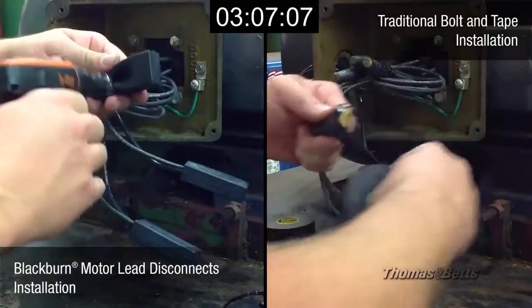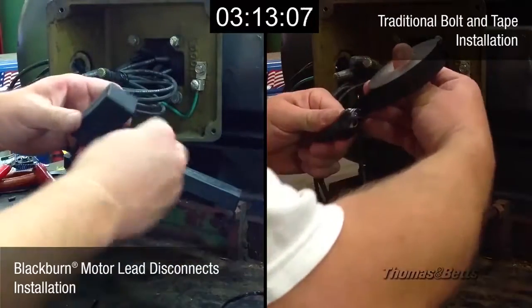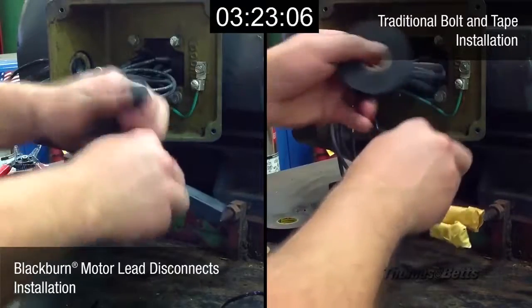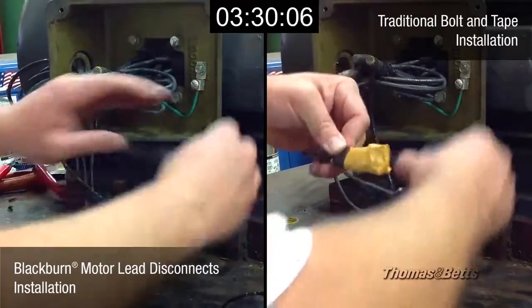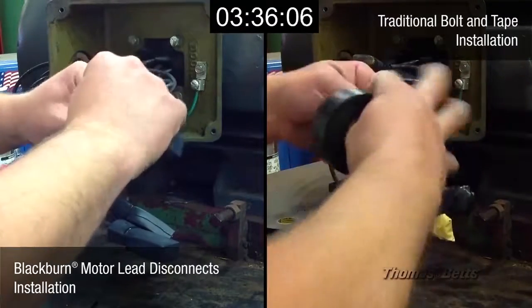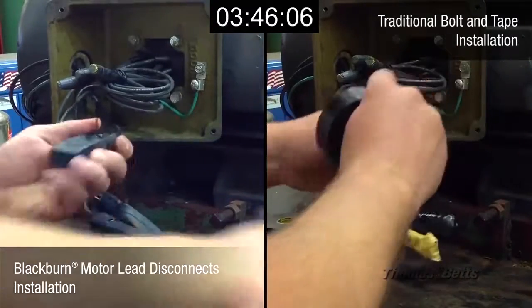The motor lead disconnects cover the wire range from number 16 through 500 MCM and meet or exceed the electrical and mechanical performance of bolted connections. The female disconnects are equipped with a high-performance copper interface to produce dependable connections. Features and benefits include: quick connections; eliminates nuts, bolts, and washers; reliable insulation with no more miles of insulating tape; simply slide on the reusable boot keeping the total assembly small enough to fit into tight motor housings; labor savings from fast snap-together assembly; quick disconnect with no knife cutting of melted tape, therefore no risk of cutting wire insulation; less motor downtime; and minimized installer exposure in hostile environments.